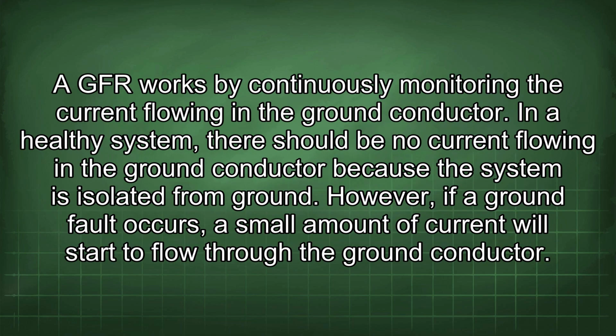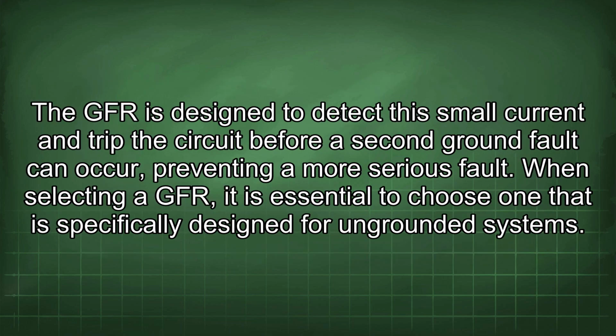A GFR works by continuously monitoring the current flowing in the ground conductor. In a healthy system, there should be no current flowing in the ground conductor because the system is isolated from ground. However, if a ground fault occurs, a small amount of current will start to flow through the ground conductor. The GFR is designed to detect this small current and trip the circuit before a second ground fault can occur, preventing a more serious fault.